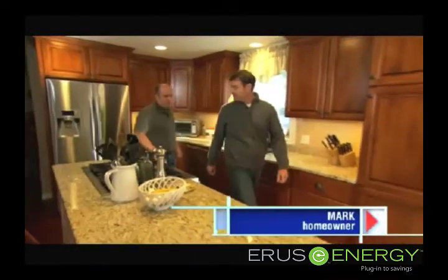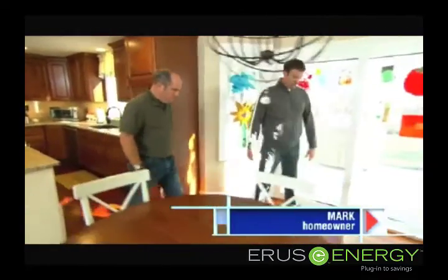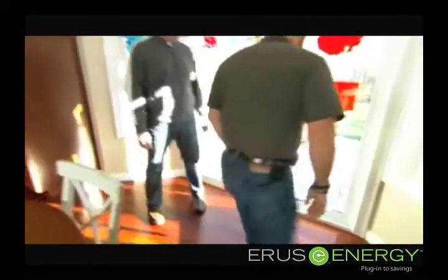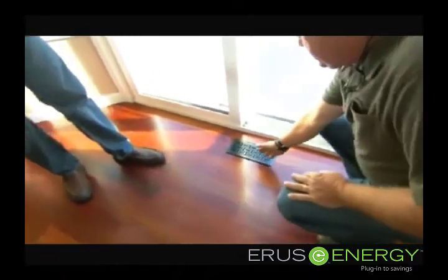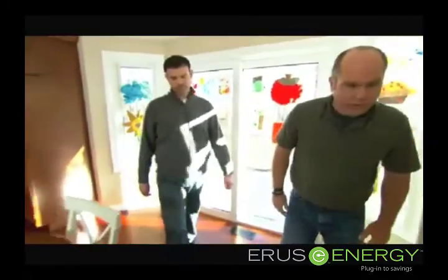Mark, your house is just beautiful. Thank you, Richie. We love it here. So what's up? Well, we wrote to you guys about our heating and cooling system. It's a forced air system. All right, I can see a supply register right here, and that's going to blow warm air in the winter right against the glass. That's good. You should have a return here somewhere. We have a return right around the corner. All right, so the air goes back to the furnace to be reheated right there.